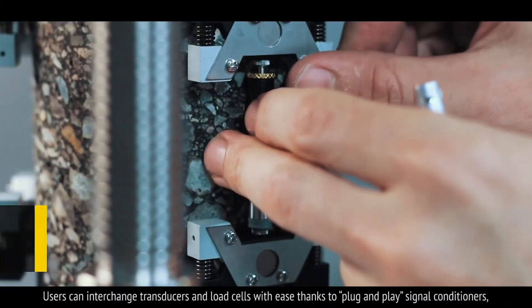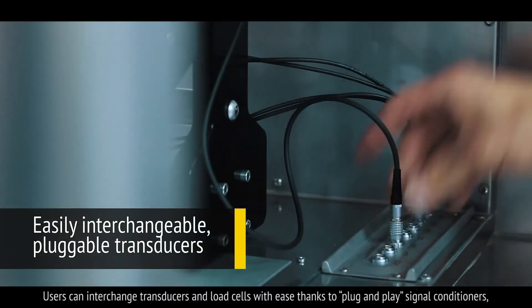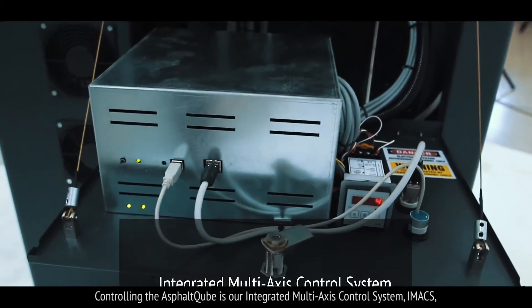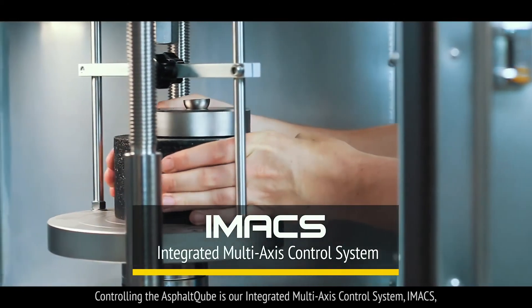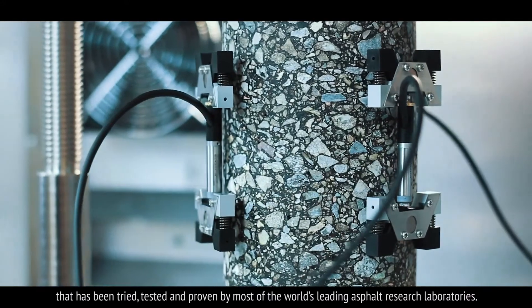Users can interchange transducers and load cells with ease thanks to plug and play signal conditioners, allowing you to quickly change between different test setups. Controlling the AsphaltQube is our integrated multi-axis control system, or IMACS, that has been tried, tested and proven by most of the world's leading asphalt research laboratories.